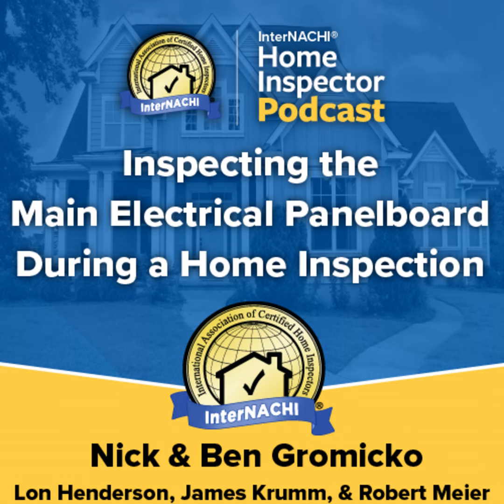Coordination between construction trades is needed to prevent these types of problems and is required by the code. Nests from pests such as bees or mice should be reported as in need of correction. Foreign debris of all types should be removed from equipment. There should not be any damage to components of the electrical panel board, inside and out, that might adversely affect its safe operation or the mechanical strength of the equipment. Parts of the panel board and its components that are broken, bent, cut, or deteriorated by corrosion, chemical action, or overheating are all defects that should be reported as in need of correction.